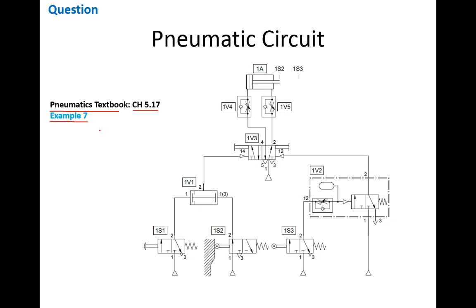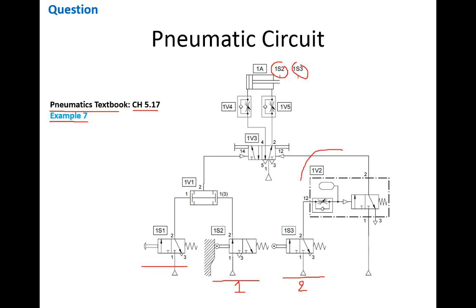This circuit is very simple in construction. It has one push button and two limit switches. This is the first limit switch and this is the second limit switch. What makes the circuit unique is the usage of a time delay valve, and the function of this time delay valve is to maintain the piston in extension for as long as the time valve is adjusted.